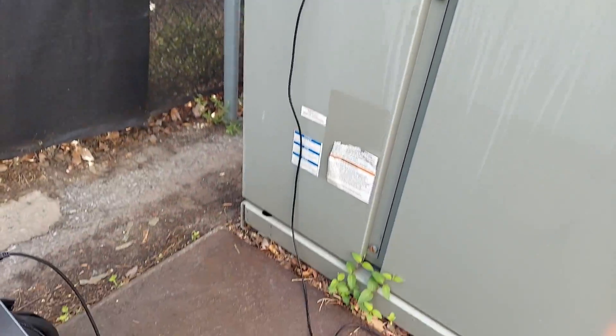Here's the key — I was going crazy. I installed the latest service pack, TechView 14.0 SP16, which is the newest one on the Trane website. But after I got the 'database out of date' error and installed SP16, the program still wouldn't launch. No matter what I did, clicking the icon just wouldn't open it.